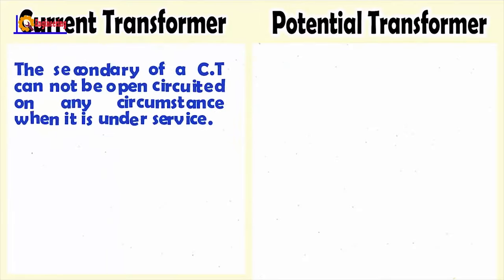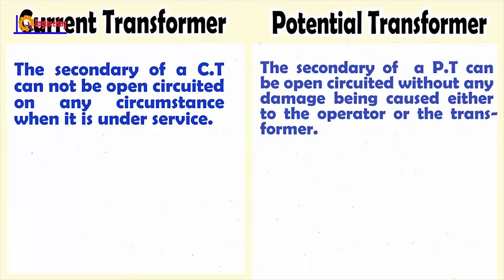The secondary of a current transformer cannot be open-circuited when it is under service. The secondary of a potential transformer can be open-circuited without any damage being caused either to the operator or the transformer.